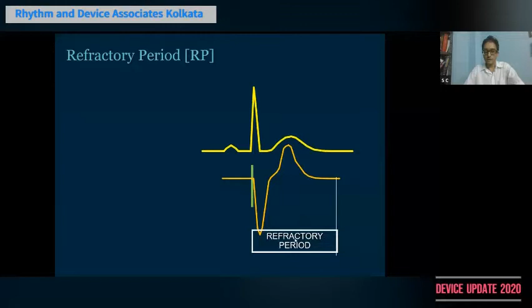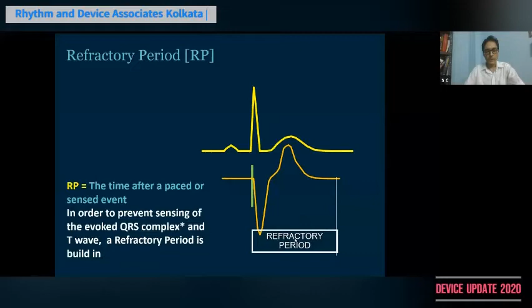by anything which happens within this refractory period. So suppose this is a ventricular pace. This is a ventricular pacing spike followed by a ventricular depolarization. A refractory period starts right after the ventricular pacing spike is given, and it encompasses the whole of the repolarization phase, because of which this T wave falls into the refractory period. It is not sensed, and therefore it does not lead to resetting of our base rate. So to prevent sensing, this refractory period is built into the pacemaker device.